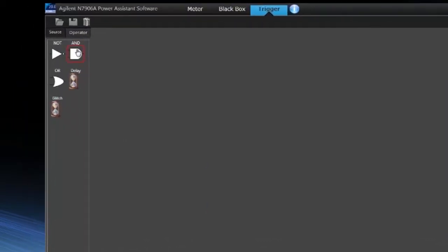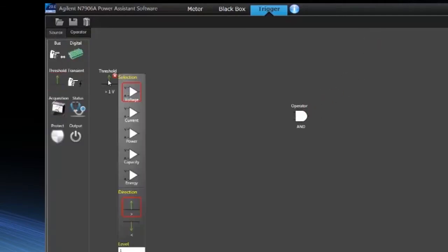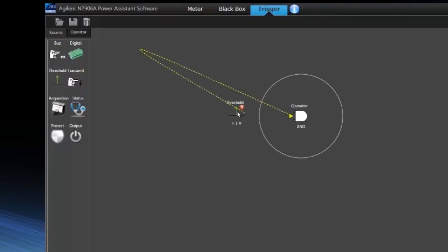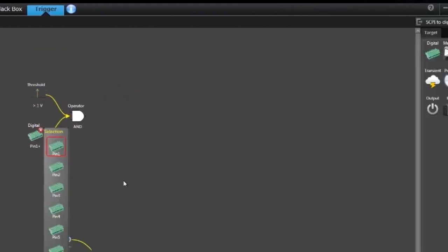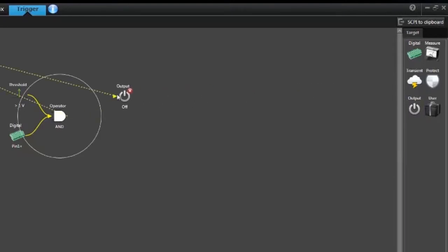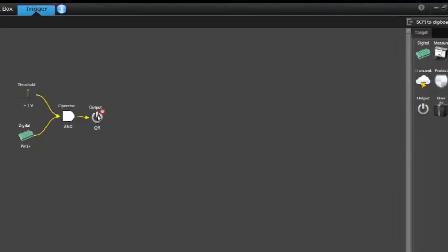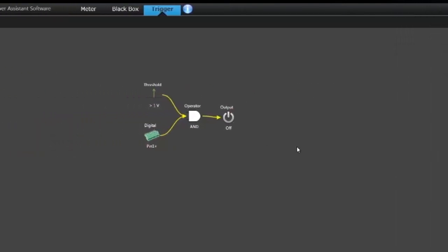So let me configure a logical trigger. We start by using an AND gate. And for my AND gate, I'll use a level trigger, and then I'll also use a digital input trigger, pin 1. And then finally, the results of this trigger condition, I want it to shut off the output. So I say output off and I add that to the output of the AND gate.